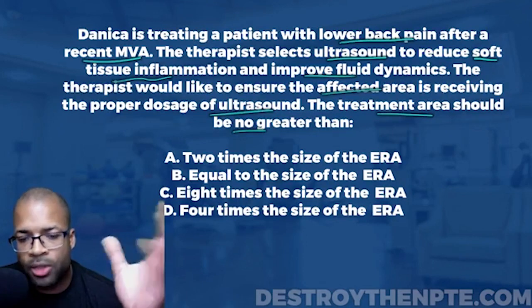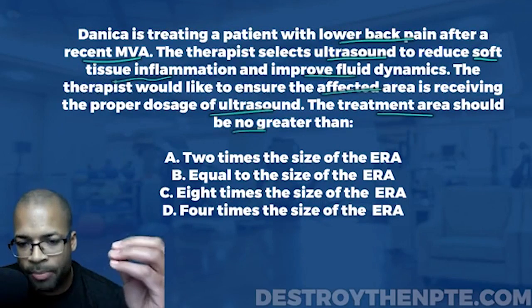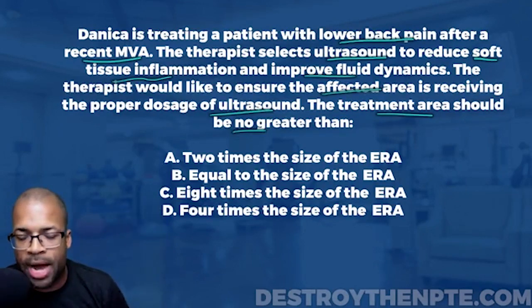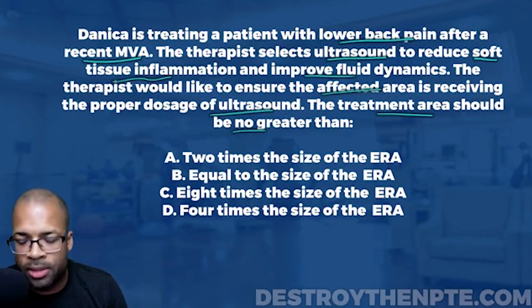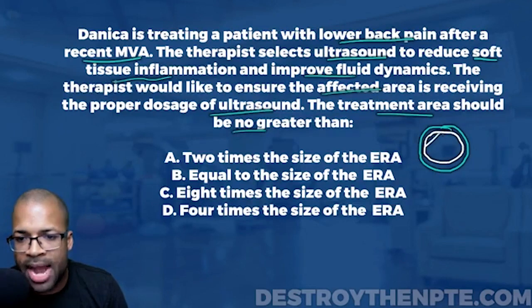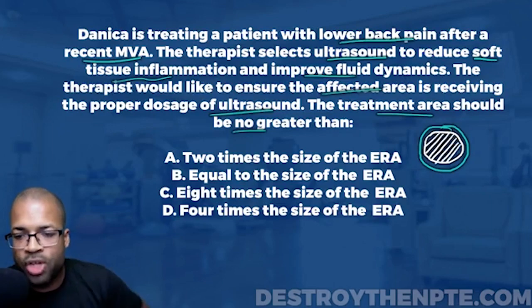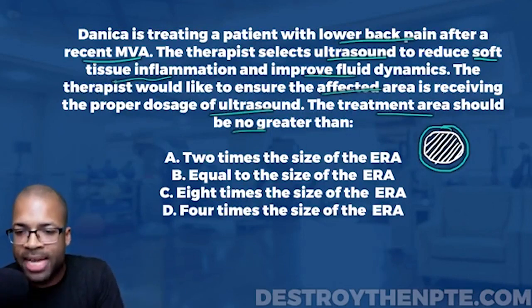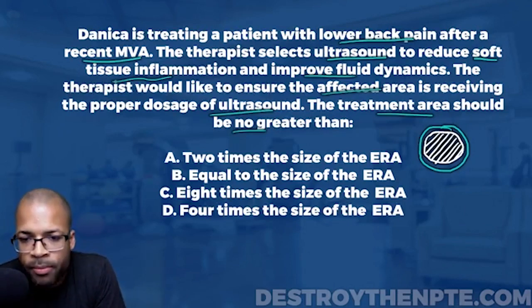Let's go over the effective radiating area principle. Envision the ultrasound head — that circular thing at the top of the transducer. Inside that ultrasound head, there's a specific space from which the ultrasonic waves actually emit. The entire ultrasound head does not produce ultrasound waves; only a part of it does. That active portion is called the effective radiating area, or ERA.